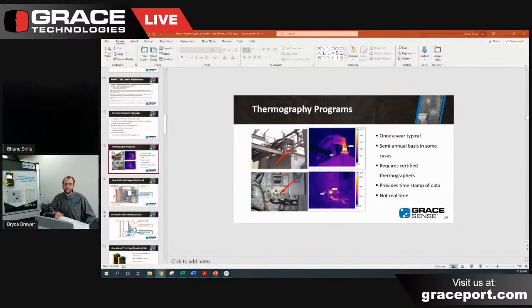I was at a hospital the other day, and there was a lady just using an infrared camera to monitor temperature. So you need to understand that people are certified thermographers when performing this maintenance task. This isn't something where you just point this gun at an asset or connection and take the measurement - you need to calibrate it and understand the emissivity settings within the different types of elements you use.